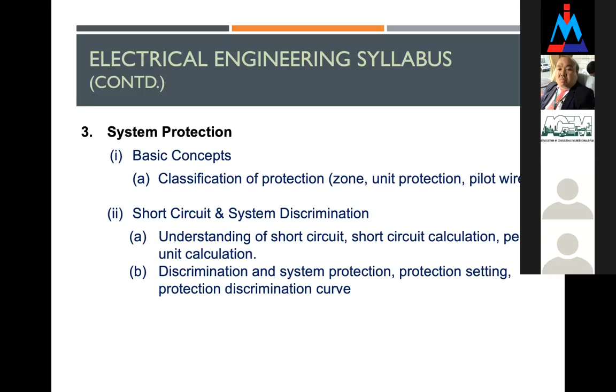When designing system protection for your project, another important terminology is discrimination, so that you can have an effective system protection for your project. We deal with protection relays and protection settings, and each relay has its own protection discrimination curve. As an electrical engineer, you should be able to advise or design a system protection with sufficient discrimination for effective protection, because we always want to isolate the problem at the source and prevent it from affecting the whole system and process.